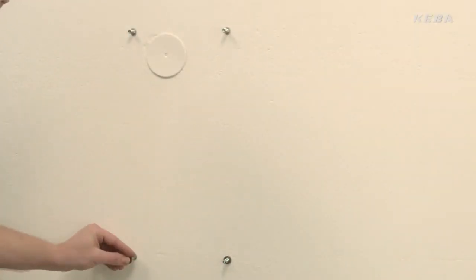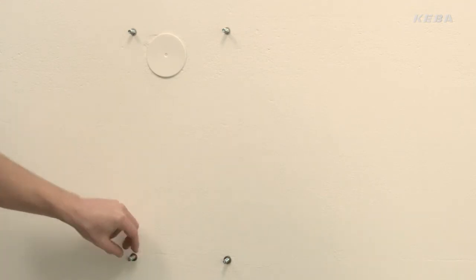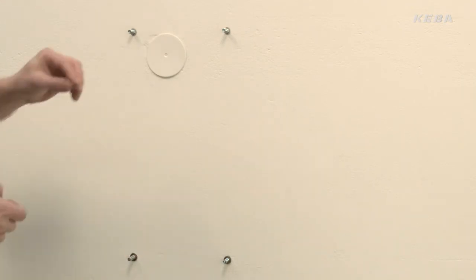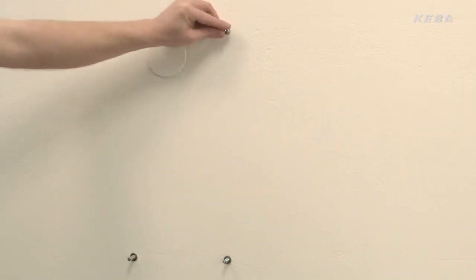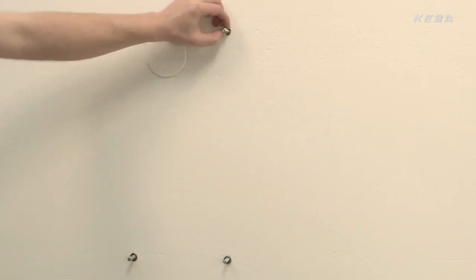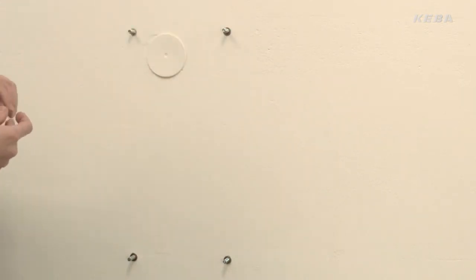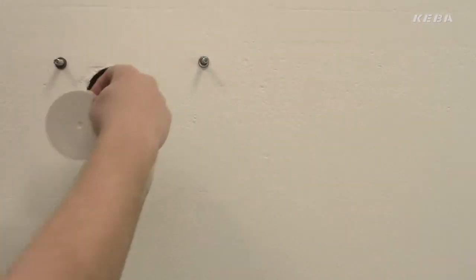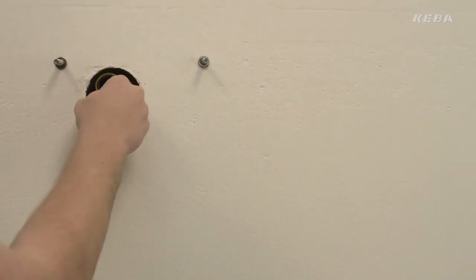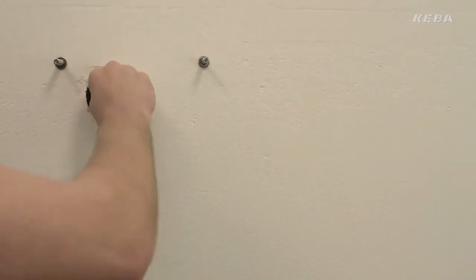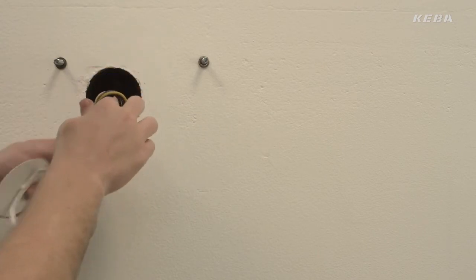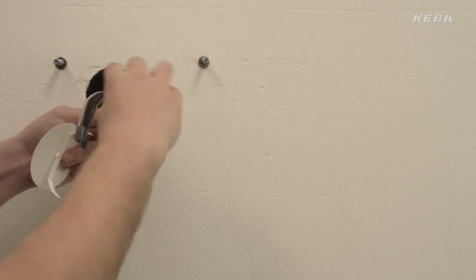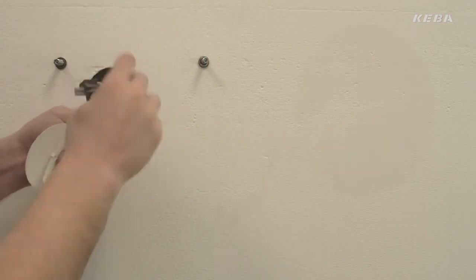For surface mounted installation, use the cable gland supplied. This prevents moisture ingress into the housing in both installation cases. Ensure that the connection cable is not live and that it is secured against being switched on.